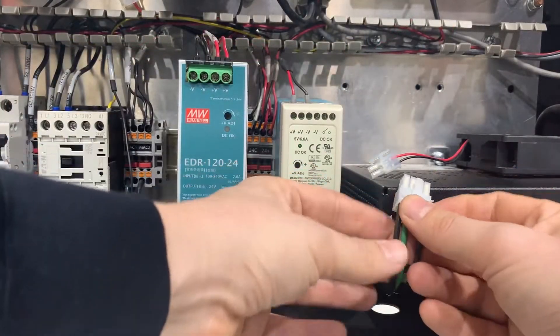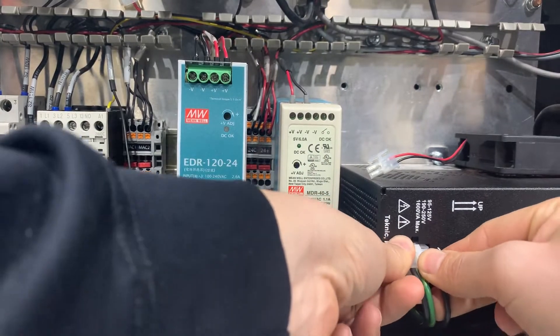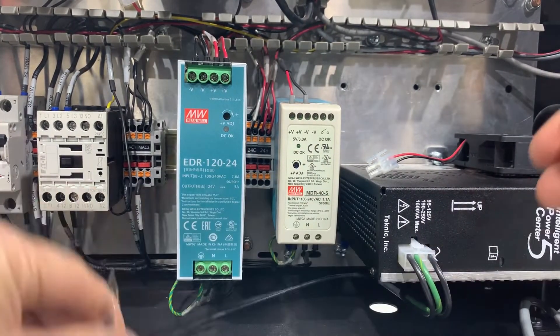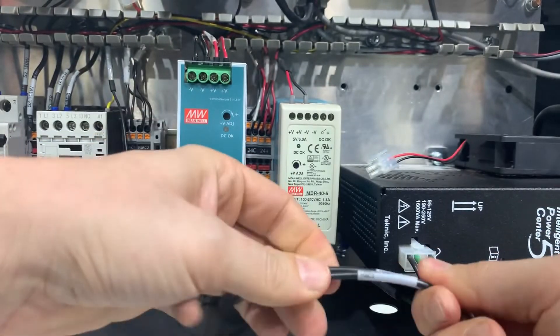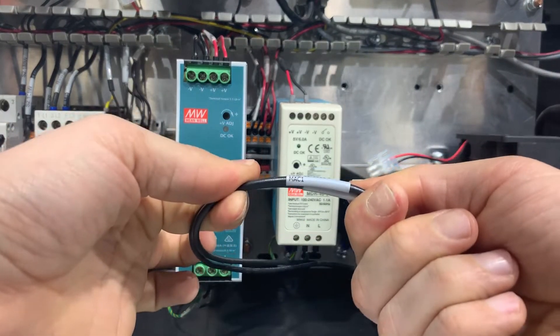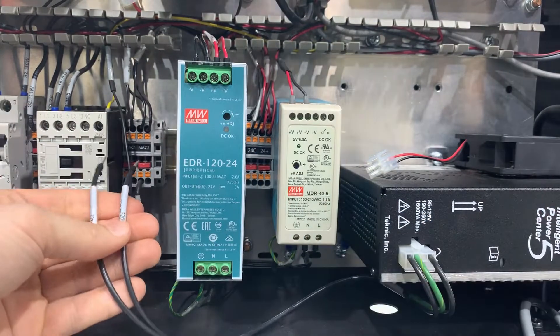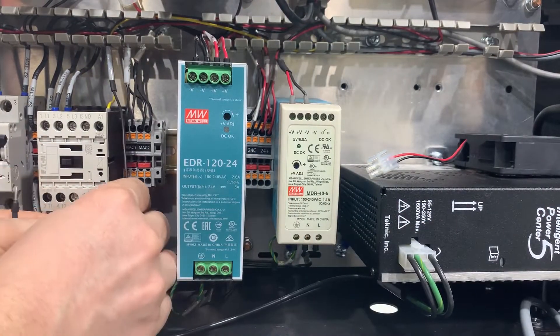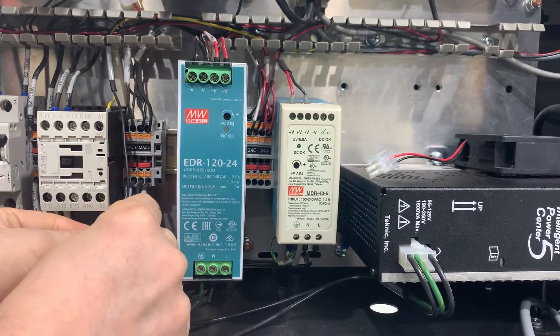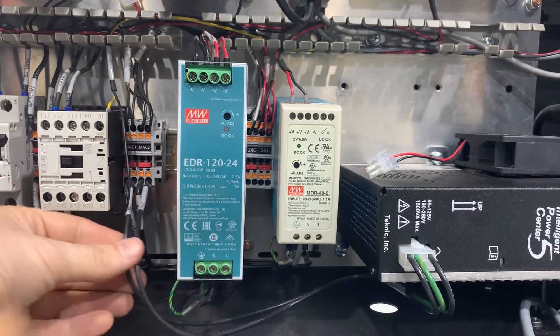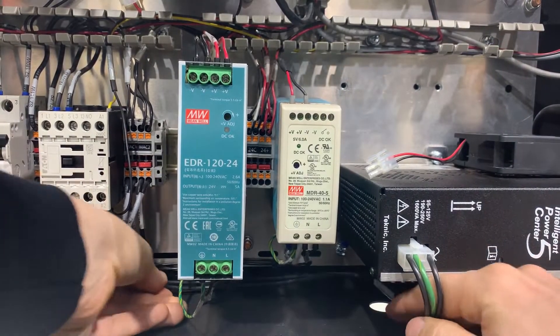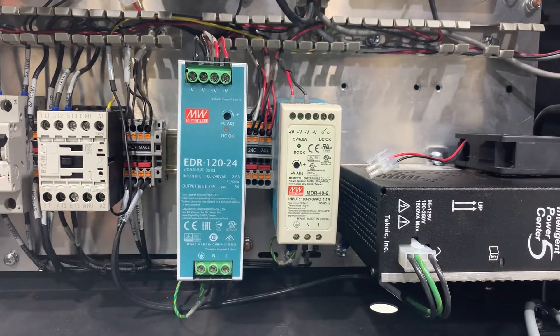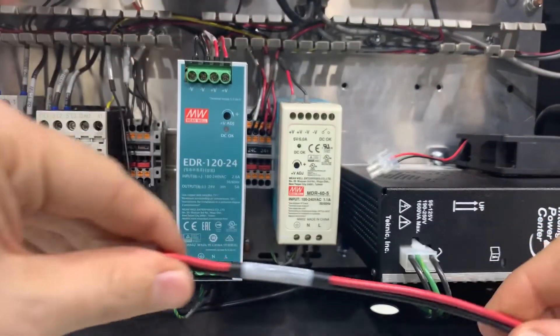Insert the white end of the AC input power supply cable into the matching connector on the power supply. It is polarized and cannot be plugged in backwards. The two free ends of the AC power supply cable are labeled MAC1 and MAC2. They insert into the corresponding terminals located on the block to the left. When routing the wires, be sure to keep them at the bottom of the box mixed in with other AC high voltage signals.